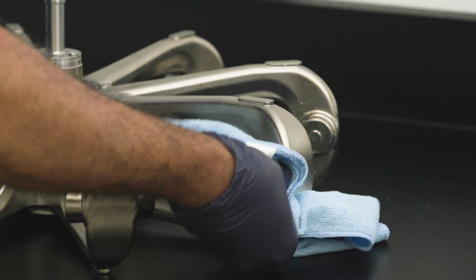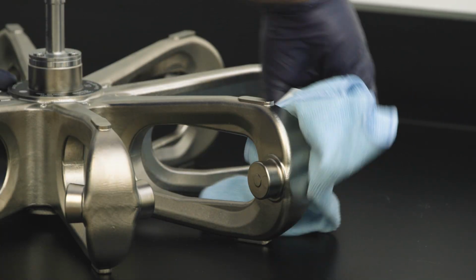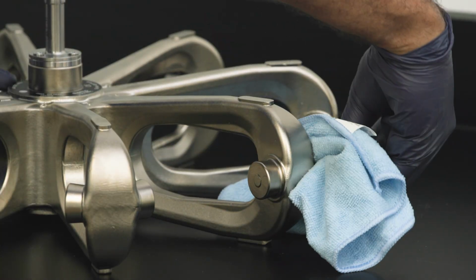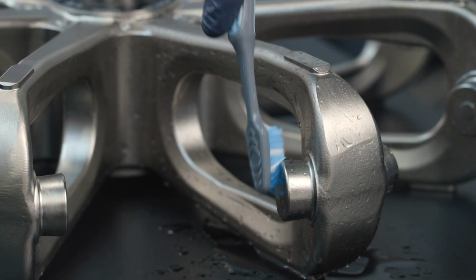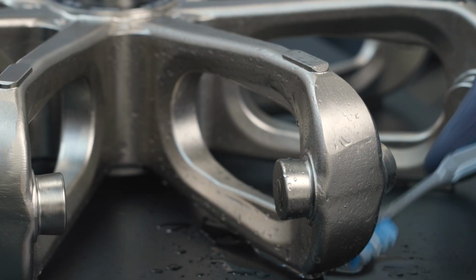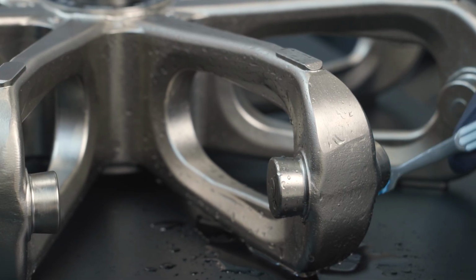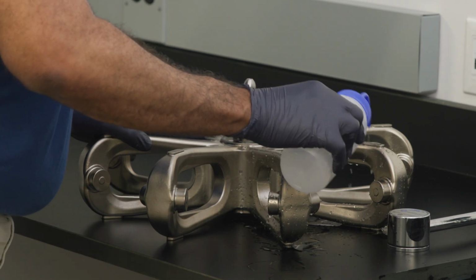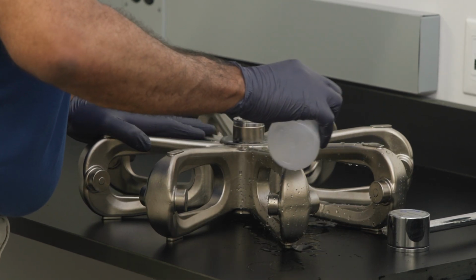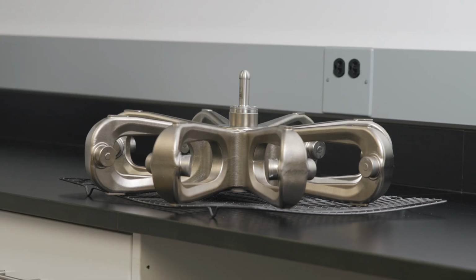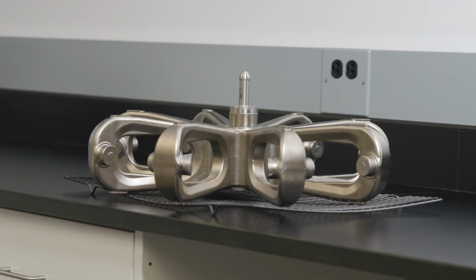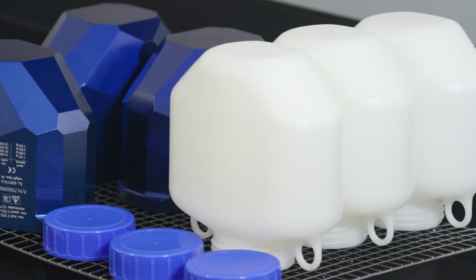Next, clean away the grease from the rotor trunnions. These are the pivot points for swinging buckets. Use a soft brush without metal bristles to remove stubborn residue. Then, rinse the rotor and accessories with distilled water. Place the rotor on a plastic grate with their cavities pointing down so they fully drain and dry.